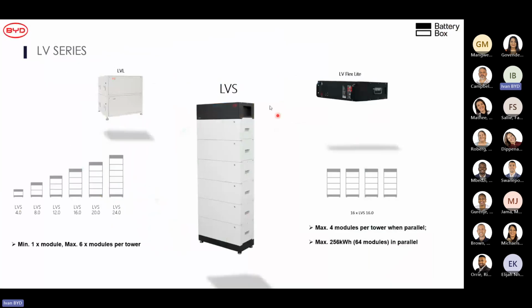Next, we've got the LVS, low voltage battery. And unlike with the high voltage batteries, we don't have to have the same number of modules in a tower. With low voltage batteries, you don't have to do that. Here's an example of 6 modules in a tower. You can have a single tower of 6, but when you parallel towers, the maximum number of modules you can have in a tower is 4.